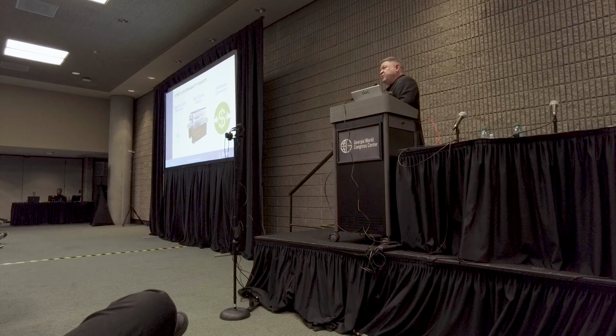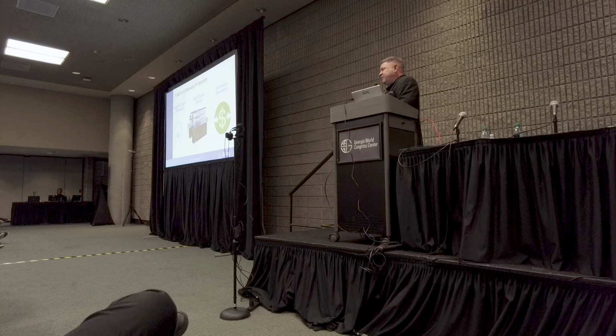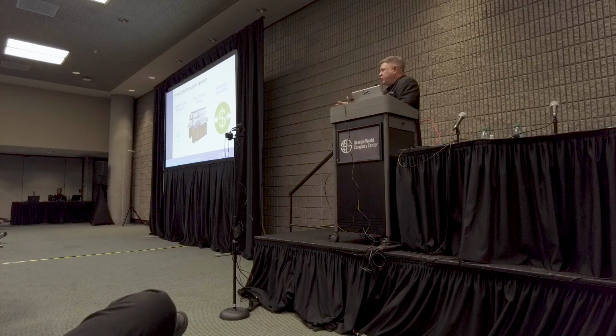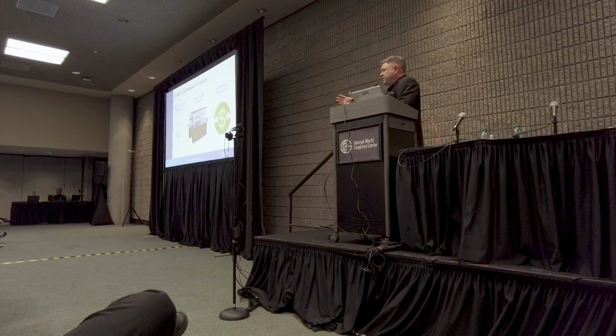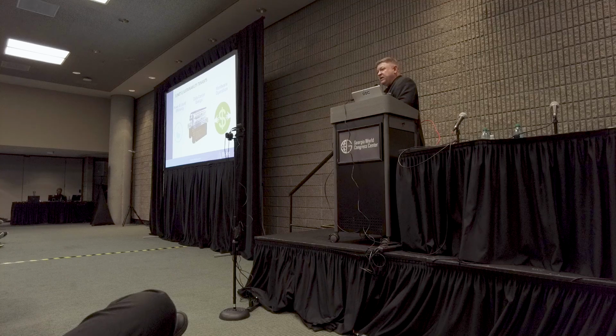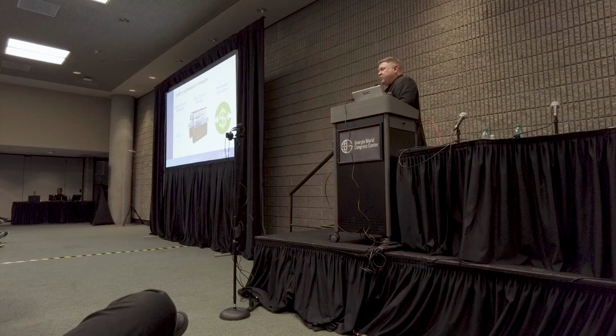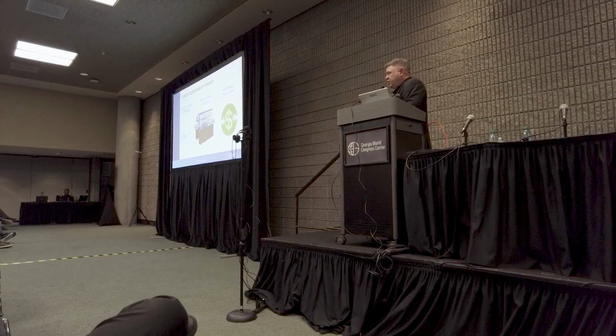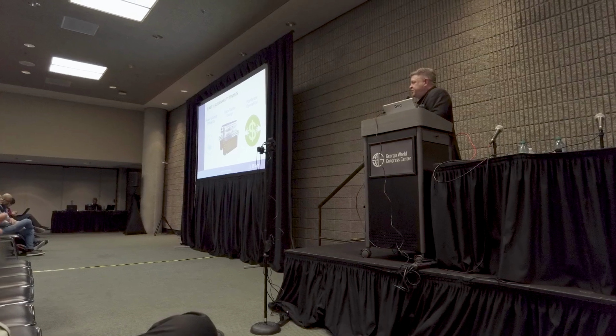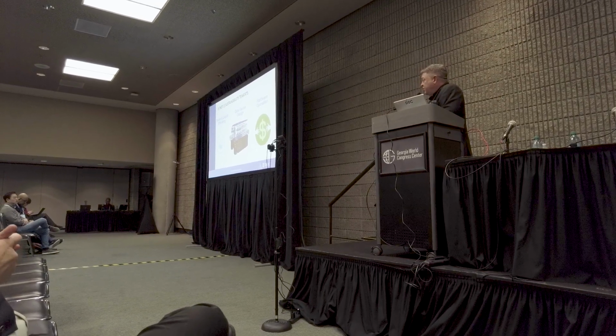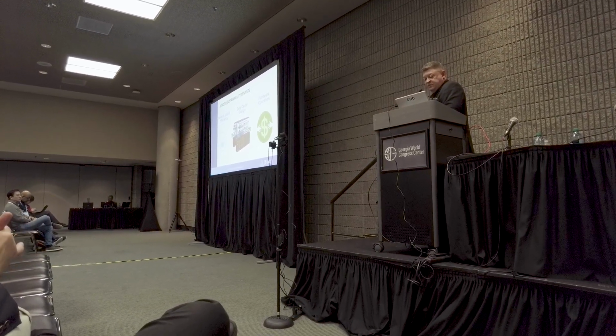So we want to make sure that if there's a solution that costs the same to build as a raised floor with hot and cold aisle encapsulation, but does 10 times more cooling at the rack level today, that seems like a better building block to start from, so we don't have to reinvest in large changes 2 to 3 to 5 years down the road when application refreshes happen.